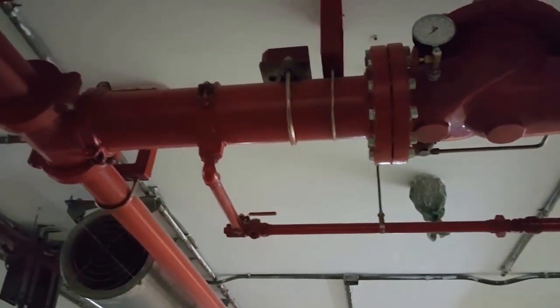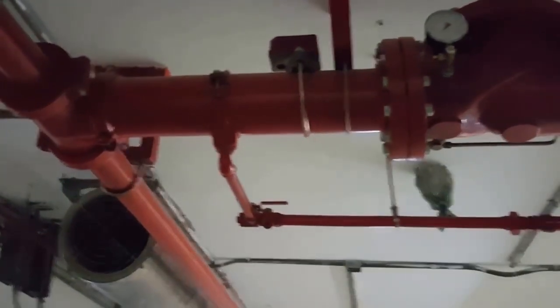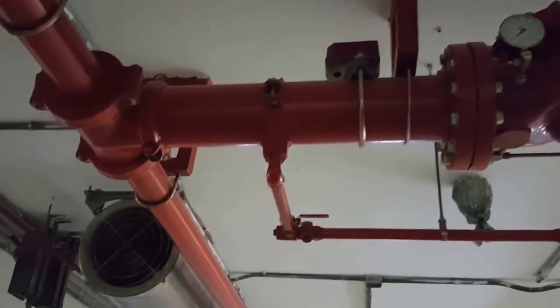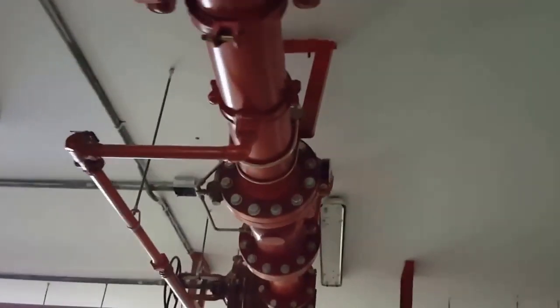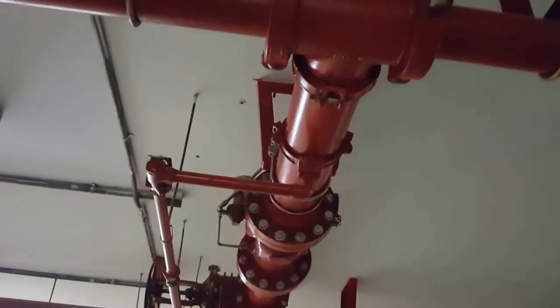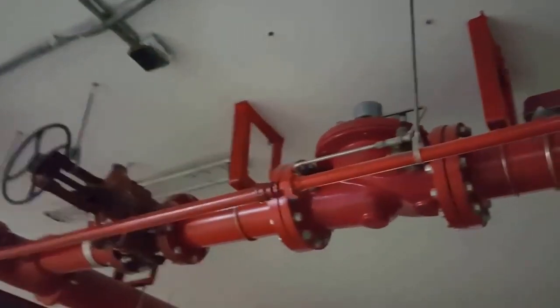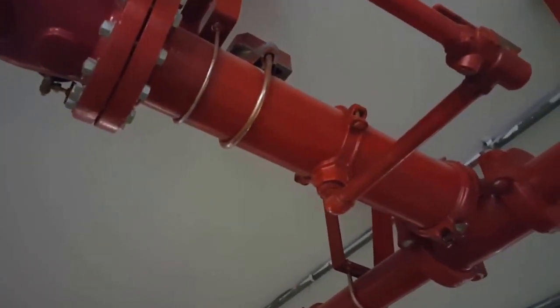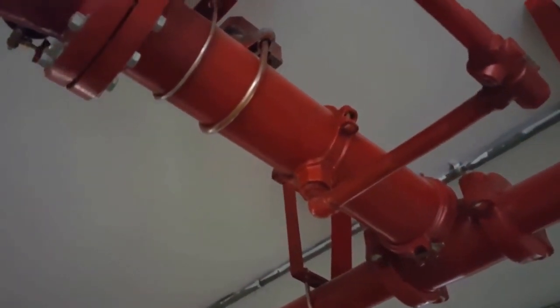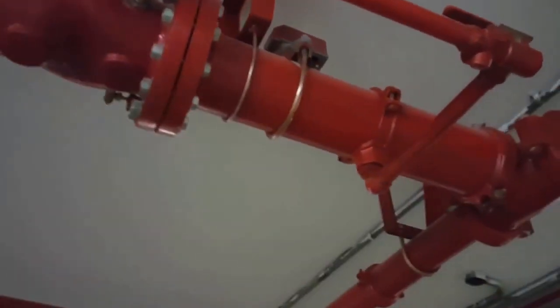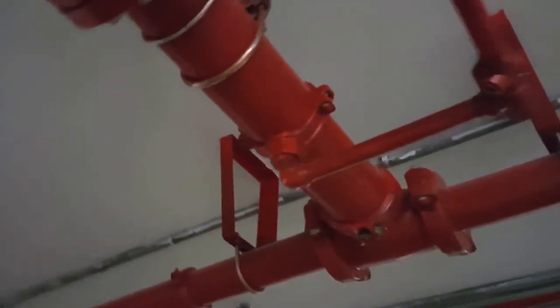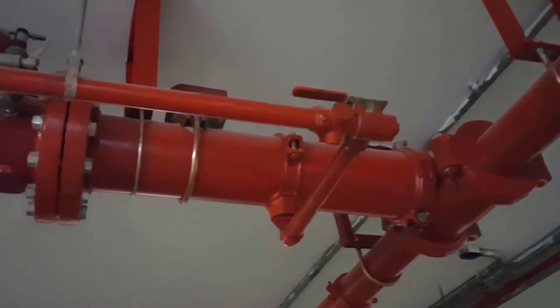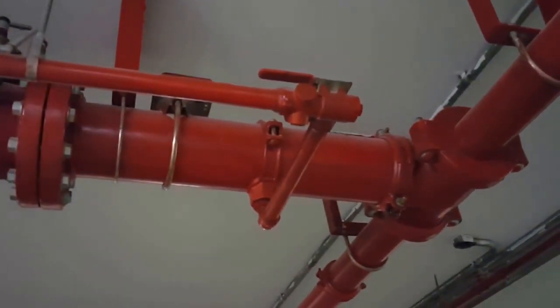I bring this video for firefighting drain pipe lines. See, this is a drain pipe line from the down with the firefighting installed here. You can see very clear, this is a drain pipe. When we want to drain the water from the firefighting pipe, we install this two-inch pipe and one-inch pipe and this one is going like that. We have to connect this drain pipe. This drain pipe is installed here from the down. This is a coupling, we installed this roof fitting with coupling and this pipe is going direct to the drainage. This water, when you drain water from this pipe, we will open this valve, a small one, so this water directly goes to the drain pipe. All water will be drained from there for cleaning purposes.